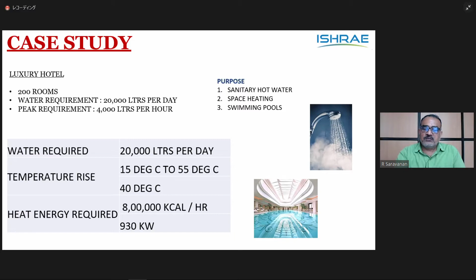Okay, so I'm going to present a case study on a commercial water heat pump for a luxury hotel which has 200 rooms. The water requirement is about 20,000 liters per day. The peak requirement is about 4,000 liters per hour. The hotel is connected with sanitary hot water application, space heating, and swimming. The temperature rises from 15 to 55 degrees centigrade. About a 40 degree centigrade rise in the heat pump is envisaged. The heat energy required is about 930 kilowatts.